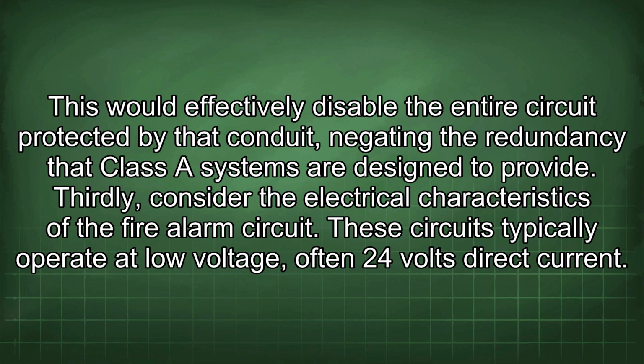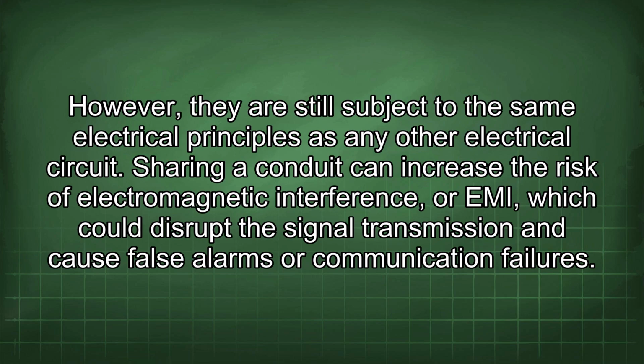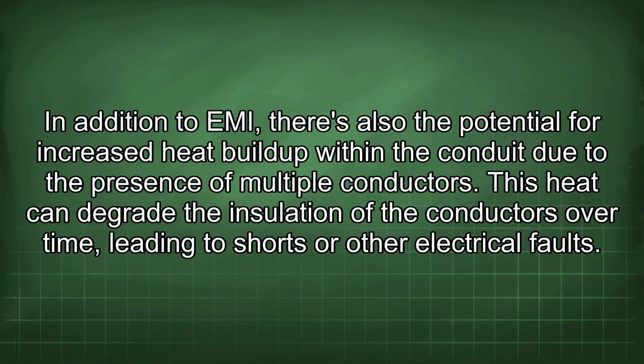Thirdly, consider the electrical characteristics of the fire alarm circuit. These circuits typically operate at low voltage, often 24 volts direct current. However, they are still subject to the same electrical principles as any other electrical circuit. Sharing a conduit can increase the risk of electromagnetic interference, or EMI, which could disrupt the signal transmission and cause false alarms or communication failures. In addition to EMI, there's also the potential for increased heat buildup within the conduit due to the presence of multiple conductors. This heat can degrade the insulation of the conductors over time, leading to shorts or other electrical faults.